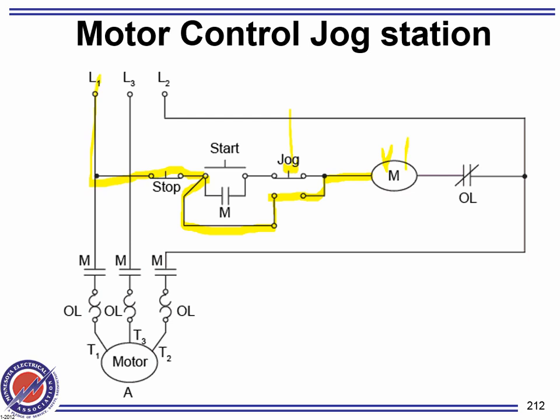It energizes the coil. Do I have any overload situation? If there is, this will open. Nothing will start. If there's no overload condition, it continues. The current continues to go back all the way, and that's how you drive. Now I can drive the motor. Once you remove your finger off that jogging station, everything stops.